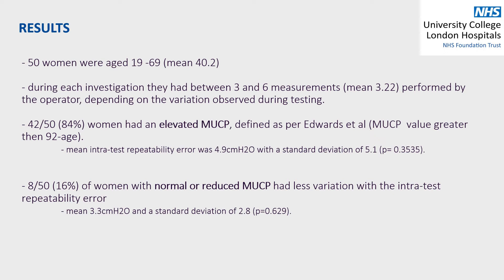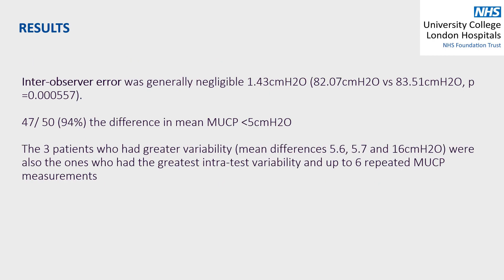The mean intra-test repeatability error in this group was 4.9 cm of water with a standard deviation of 5.1 cm of water. In contrast, eight women with normal or reduced MUCP had less variation in the intra-test repeatability error of mean 3.3 cm of water and a standard deviation of 2.8 cm of water. Inter-observer error was generally negligible at 1.43 cm of water, and in 94% of the traces, the difference in mean MUCP was less than 5 cm of water.